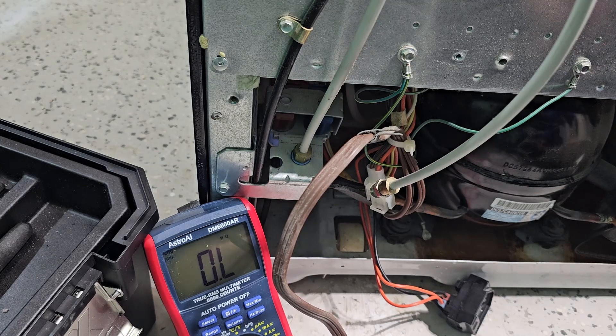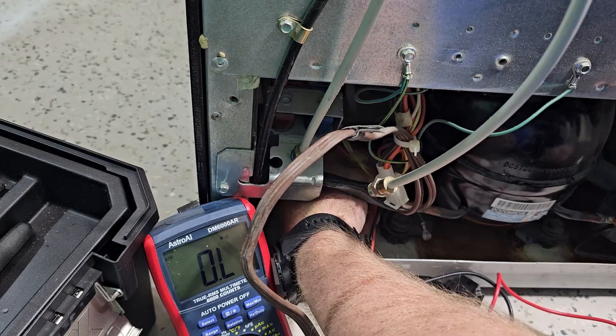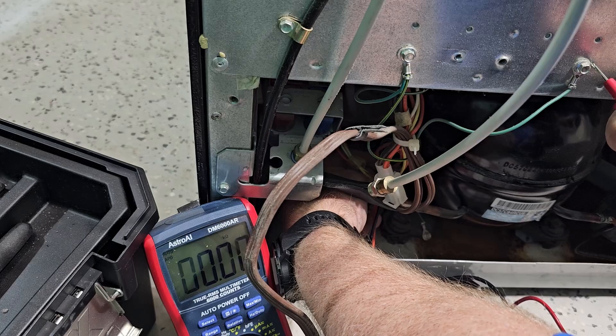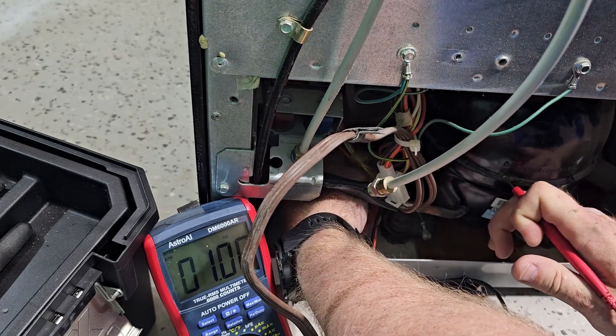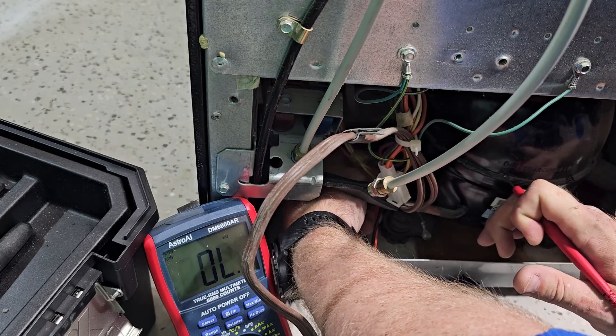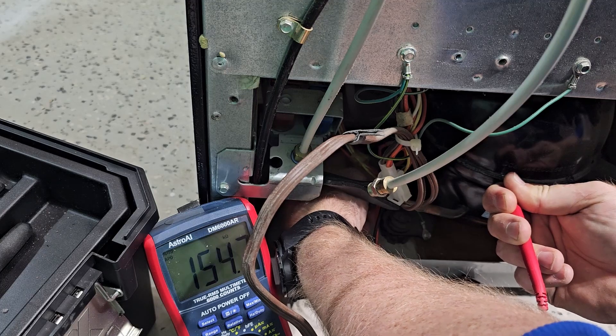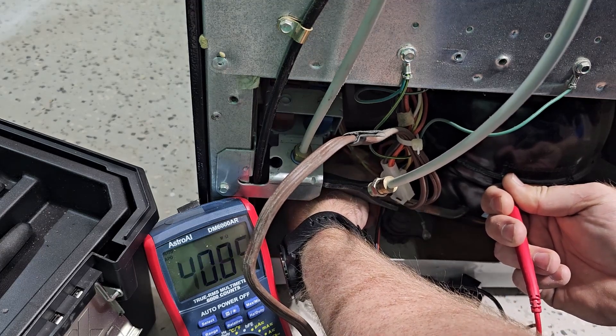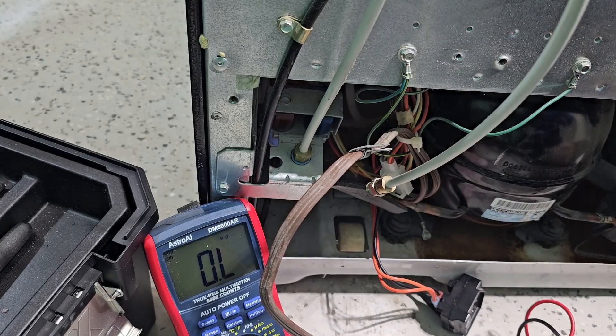There's one more check you have to do for the wiring. Put your meter lead on one of those pins and then touch it to the actual case of the compressor. You may have to scratch away some of the black paint on there. You should be getting infinite resistance - it should read OL. We got OL on all the pins, which is good. That means our compressor is electrically okay. It could still be seized inside, but electrically it's doing fine.